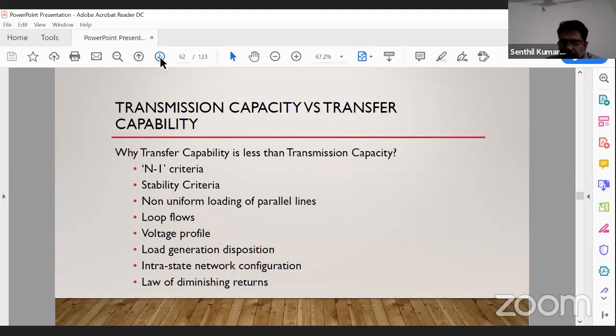In transmission capacity, suppose you carry out one transmission line with twin-moose conductor. Twin-moose conductor carrying capacity is 1000 megawatts possible. That is the transmission capacity. Is it possible to allow transmission capacity of 1000 megawatts? No, it is not possible.